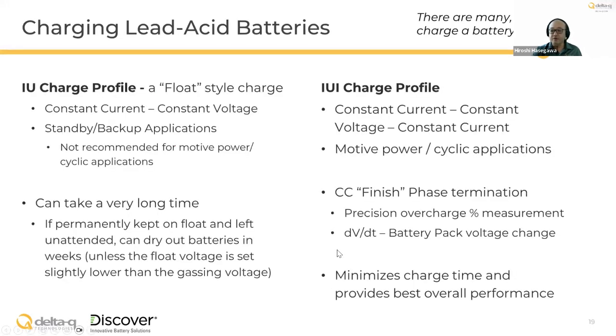There are many different ways to charge a battery. The most common methodology is what we call IU, or constant current, constant voltage—some nickname it float style charge. You see this approach in stationary applications such as battery backup, or off-grid applications such as solar battery storage. The float voltage may also be slightly lowered if the battery is permanently kept on float. Although simple, the IU charge profile can take a very long time.